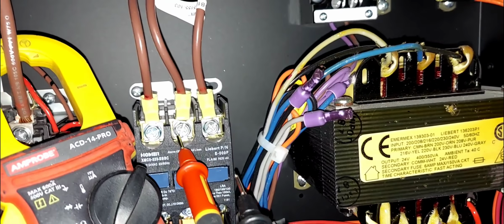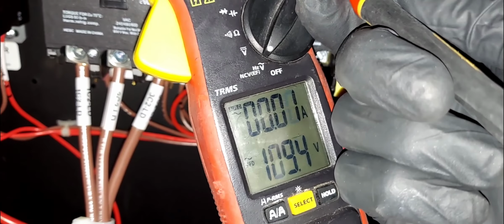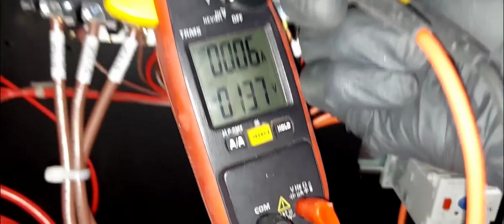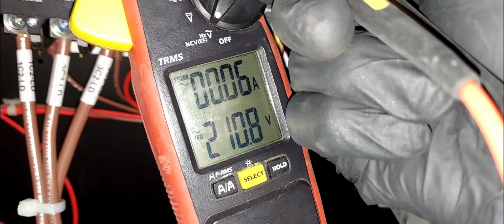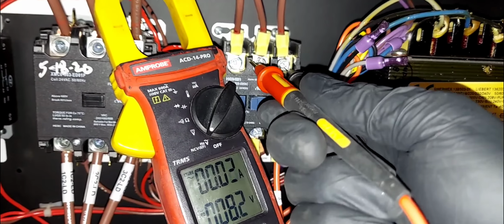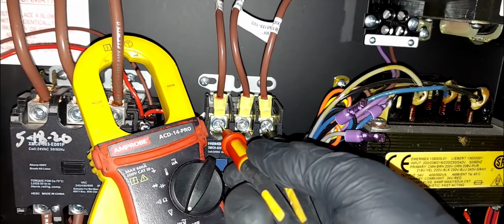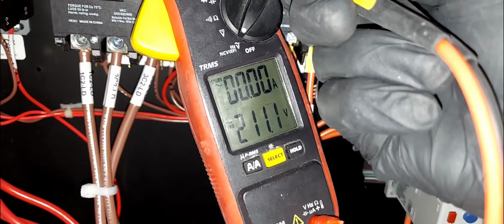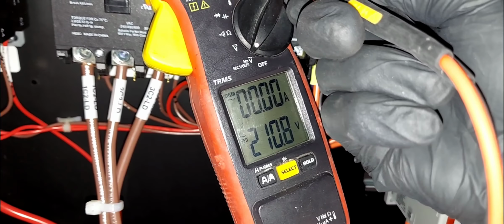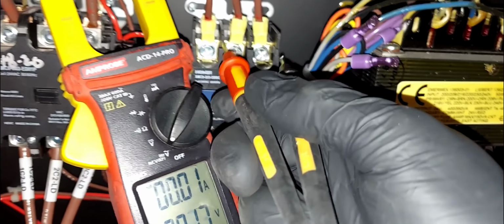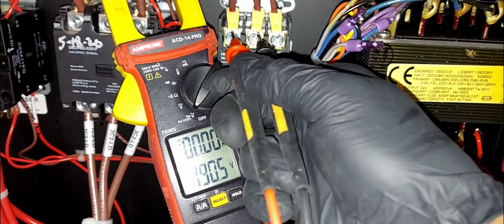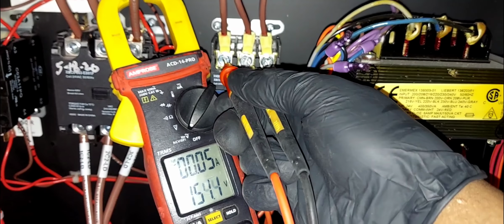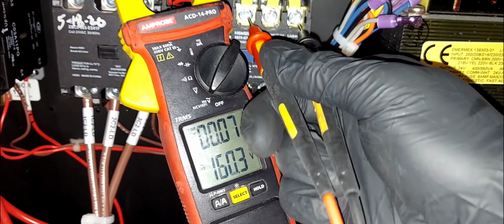All right, so I'm gonna go ahead and check, because you know I have 3 fuses that feed the main fan. I'm gonna check to make sure that they are closed and my power is good. All right, so that's good. That's good. All my 3-phase fuses are good. I'm getting 3-phase power. Okay. See, real time. All right, so that's checked out.